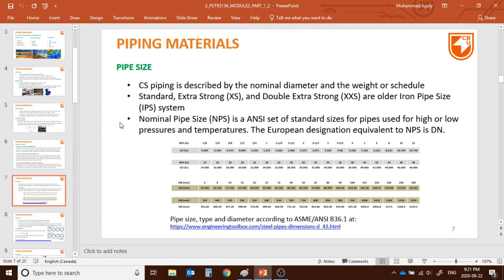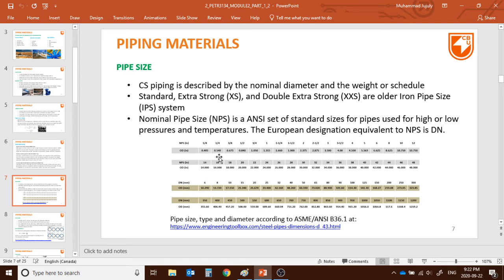This is an equivalent chart for NPS and outer diameter. For instance, if NPS is 1/8 inch, what is the outside diameter? If NPS is 8 inch, what is the outside diameter? Interestingly, the NPS value and outer diameter are different numbers. For example, NPS 14 has an outer diameter of 14 inches, and NPS 36 has an outer diameter of 36 inches, but NPS 12 has an outer diameter of only 12.75 inches.